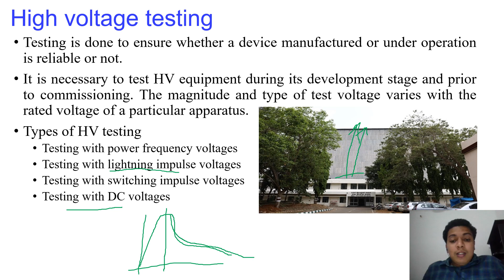Now let us see what is meant by testing with power frequency voltage. I think you are able to see this voltage level, around 600 kV. You can see the equipment and the geometry required to withstand this, and notice the height, like inside that building you just saw. That is the level of voltage we are working with.